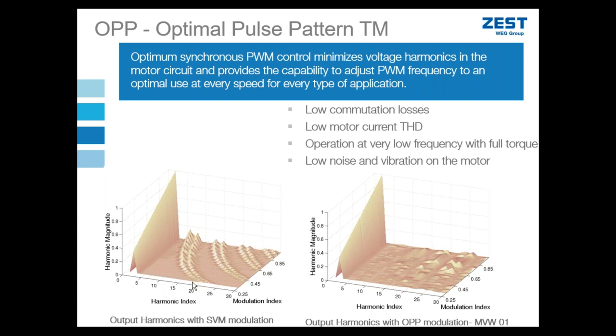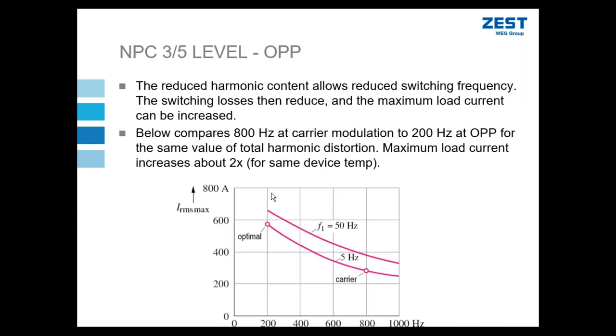However, our non-useful or wasted harmonics also increase as we increase our modulation index. And you can see that at full load, at full modulation index, in this particular case, my 11th and 13th harmonics, for example, are a problem, and so on as I get to the higher order harmonics. You can see these harmonics are quite high. With optimal pulse pattern switching, through some very fancy algorithms, at any given modulation index, by changing my switching frequency and which vectors I switch, I'm able to almost eliminate a lot of the higher order harmonics. So this has a very profound effect on my VSD itself.